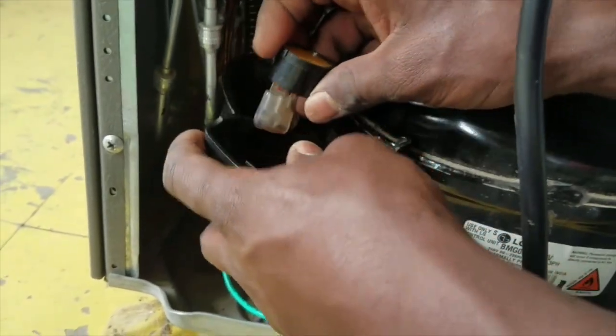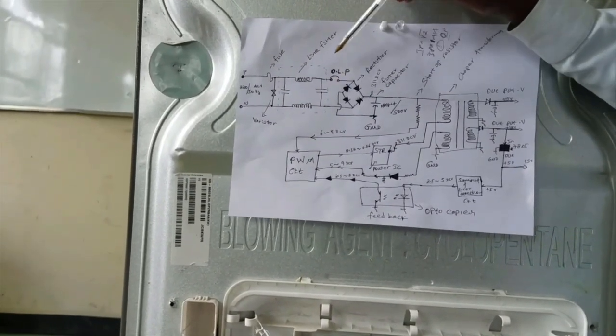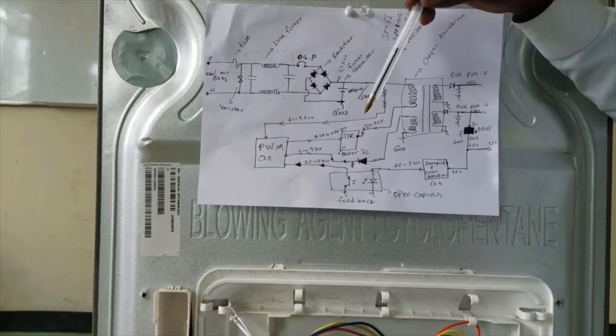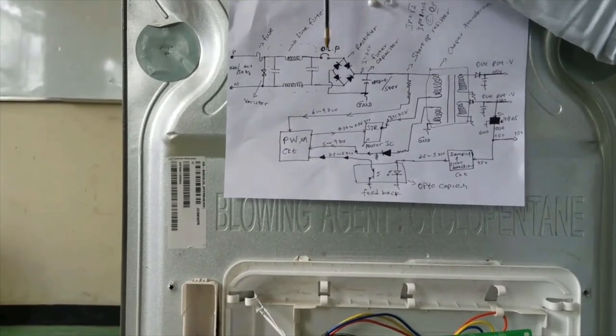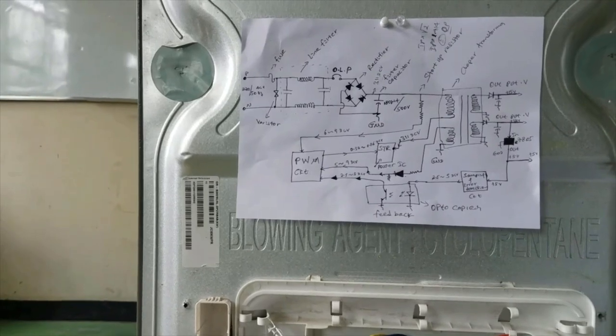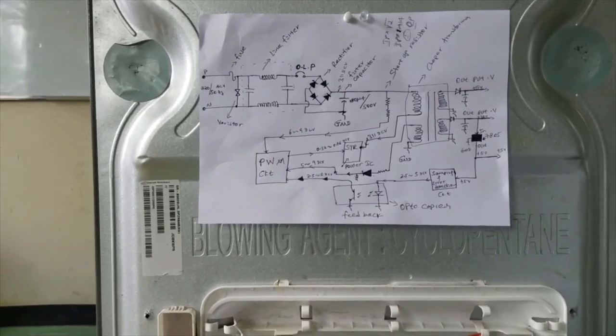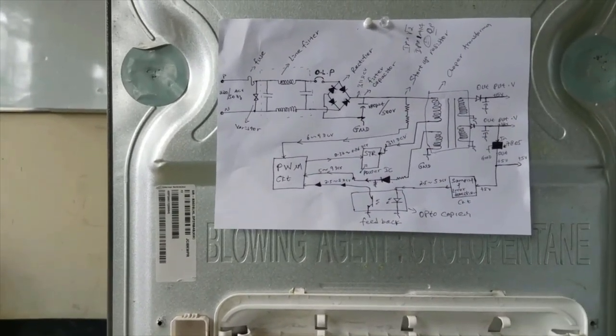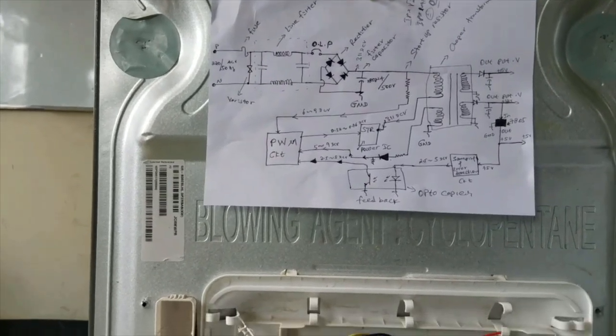Now we are replacing with the new OLP. We have to understand why the OLP became defective. This OLP is directly placed on the 220V line. The problem may be because of overcurrent in the power supply circuit, or the OLP can be defective because of an overheated compressor. Let's check the functionality of the compressor — if the compressor is defective, it becomes overheated, and continuously the OLP becomes open.